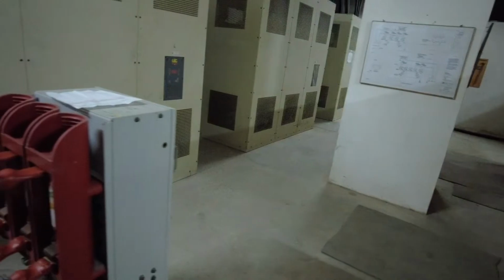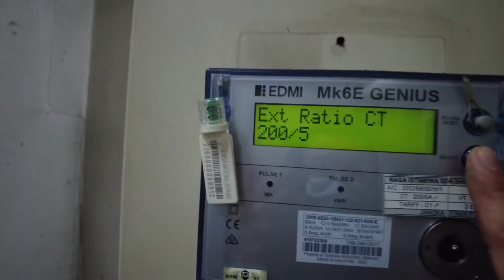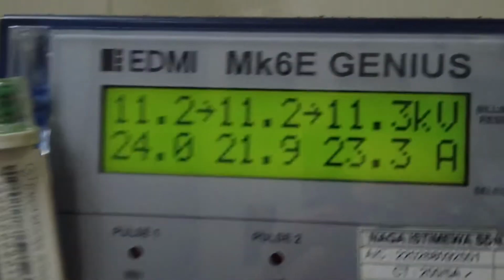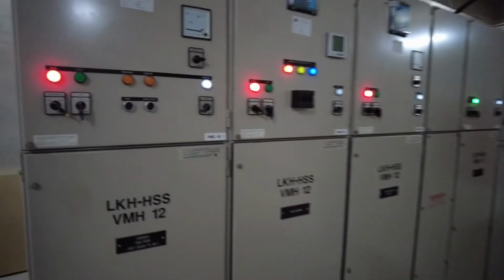Alright, before we go to the next LV room, let's just check the HV room first, because just next to the genset room. Alright. This is the main HV room, 11 kV. Okay. Here we have 3 units of cast resin transformer. Let's check the loading. Okay, this is one incomer. Check the other incomer. Alright. This is the 11 kV VCB panel. Okay. Do make sure all the heater is in good condition. Alright, make sure the room is dry. Here we have the temperature controller faulty.